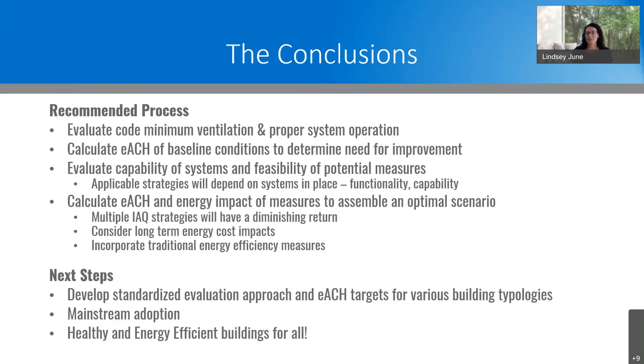Next is to use the EACH method to determine your baseline IAQ. So the extent of airborne exposure reduction strategies that may be needed is dependent on the current airborne pathogen exposure risk that's in spaces currently. So once the need for improved IAQ is determined, then survey the systems in place to determine applicable strategies. And these strategies will be dependent on the existing HVAC system functionality and capability. And then finally, calculate the EACH and energy impact of potential measures to assemble the optimal scenario. And remember that stacking strategies will result in diminishing returns. Also consider long-term energy cost impacts of measures and not just upfront implementation costs.